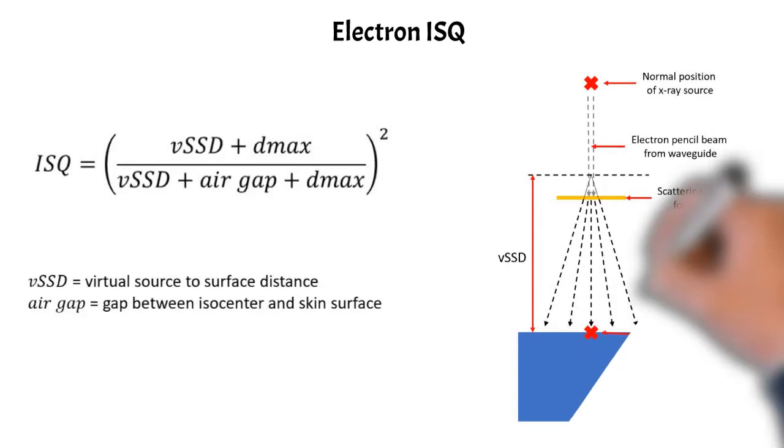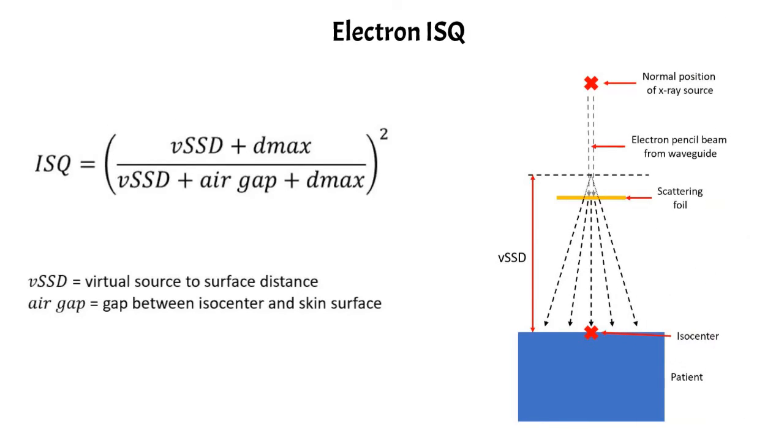And the reason for that is because it comes from the differences in the treatment head when you're in electron mode versus photon mode. And so I'll draw out electron mode here. At the top there, that's normally where your tungsten target would be. So that's where all of the photons are coming from.